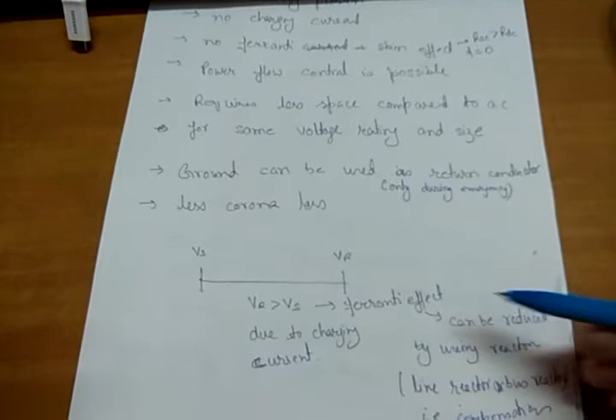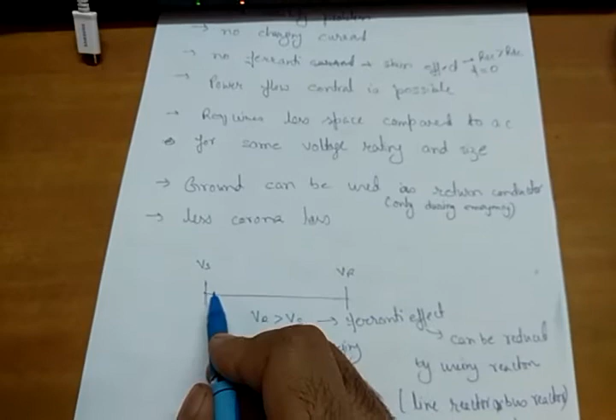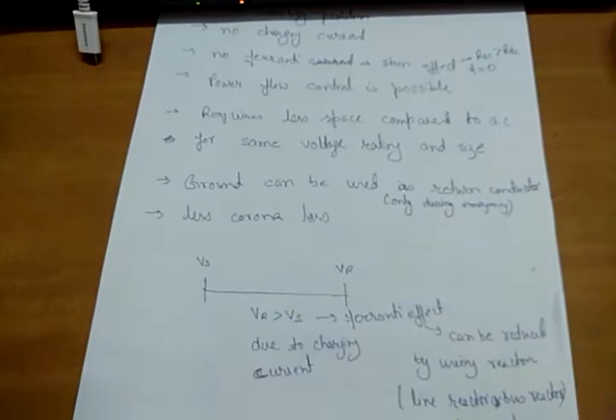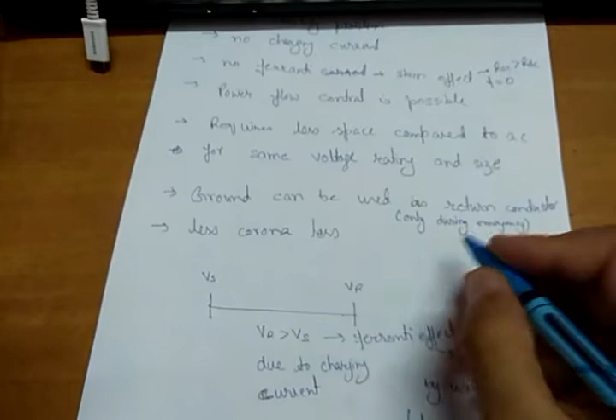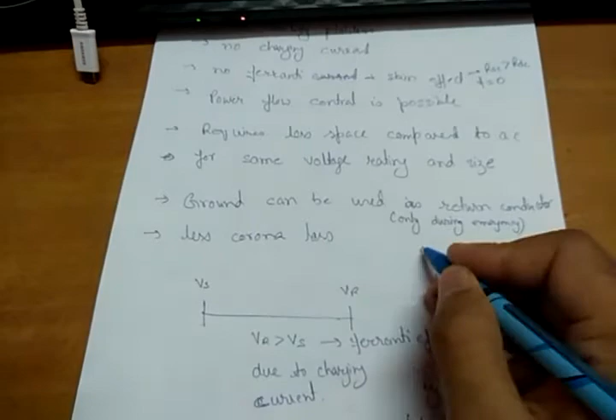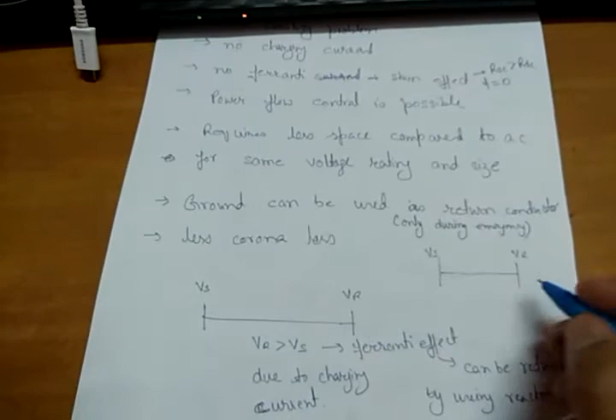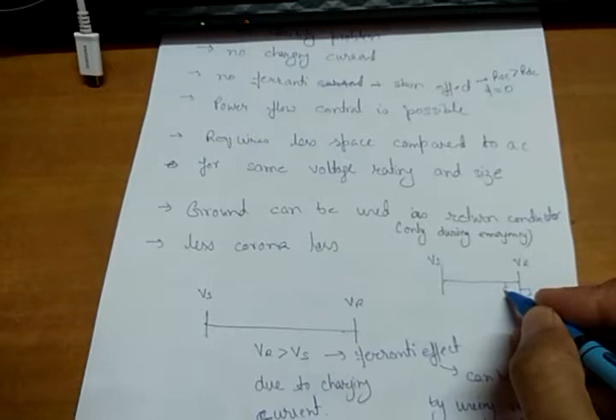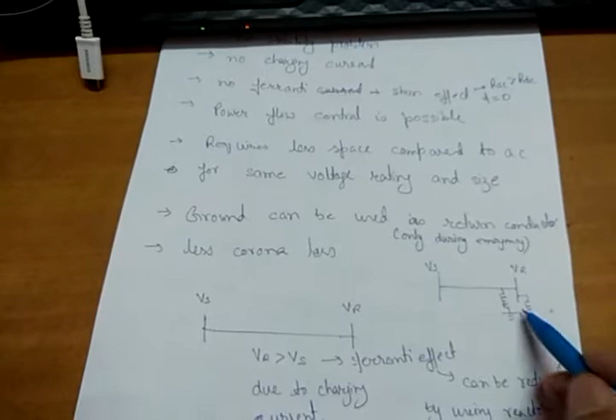How can we reduce this Ferranti effect? Suppose the voltage at this end is higher than the voltage at this end, means reactive power here is more as compared to the reactive power here. So how can we reduce the reactive power here? Simply by using compensation, by using a reactor here. Suppose I have one bus here. This is VR, this is VS. If the voltage here is more as compared to the voltage here, I can simply use a reactor here, or here. This reactor is attached to the line, that is why it is called a line reactor, and this reactor is attached to a bus, and this reactor is called a bus reactor.